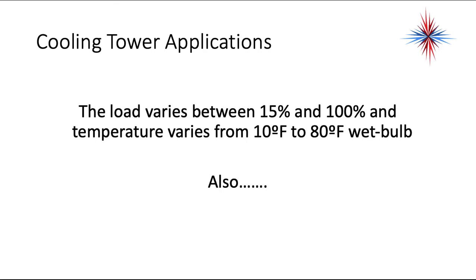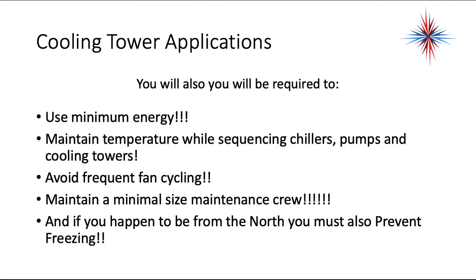When the load varies between 15 and 100 percent, the temperature varies from 10 degrees Fahrenheit to 80 degrees Fahrenheit wet bulb, and you need to use minimum energy. You need to maintain temperatures while sequencing chillers, pumps, and cooling towers. You need to avoid frequent fan cycling — we don't want the fans on the towers coming on and off too much. We need to maintain a minimal size maintenance crew, and if you're in the northern part of the country, you must also prevent freezing of the water.